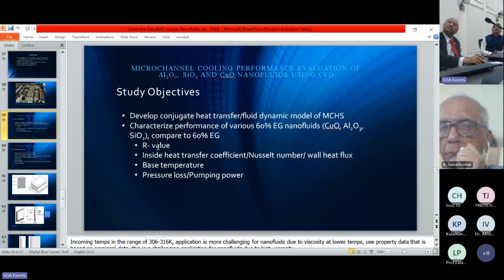We find the thermal resistance value, and if thermal resistance is lower, the heat transfer coefficient is higher. Inside, the heat transfer coefficient relates to heat flux, which comes from the high temperature, high power chips running. We calculate the base temperature on which the chips are mounted, and once the base temperature is lower, we know it's cooling a bit better. We also calculate the pressure loss and how much pumping power we invest for pure liquid versus nanoliquid.